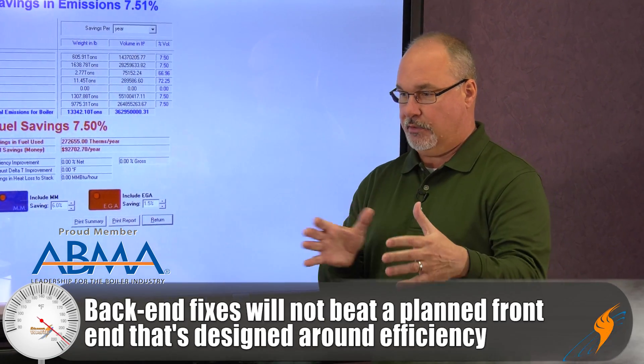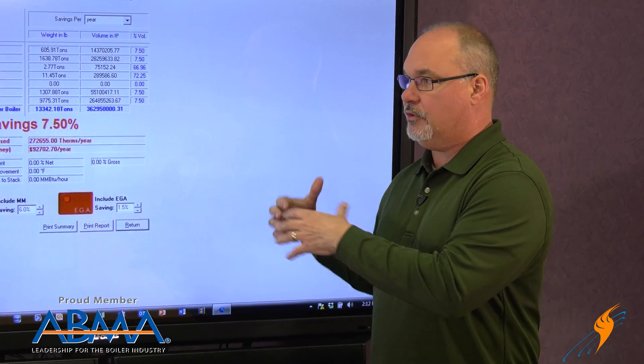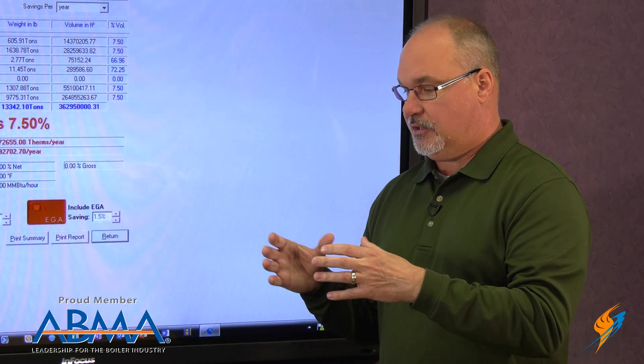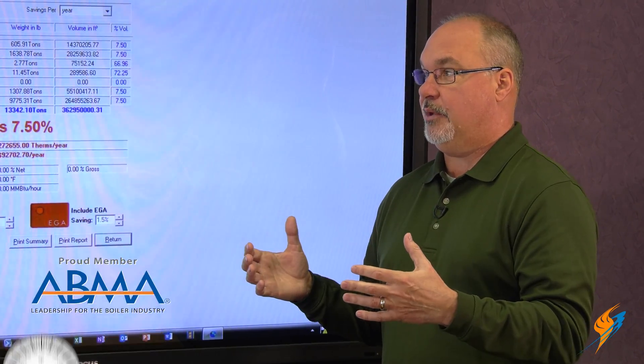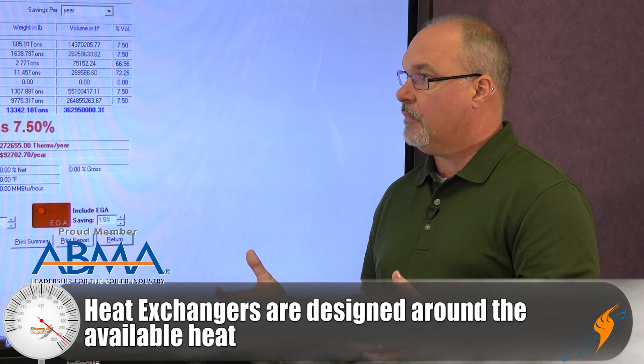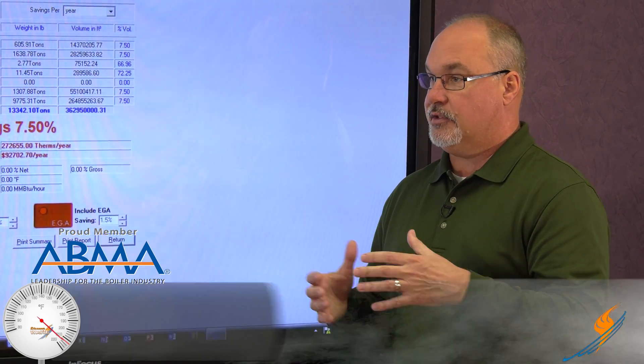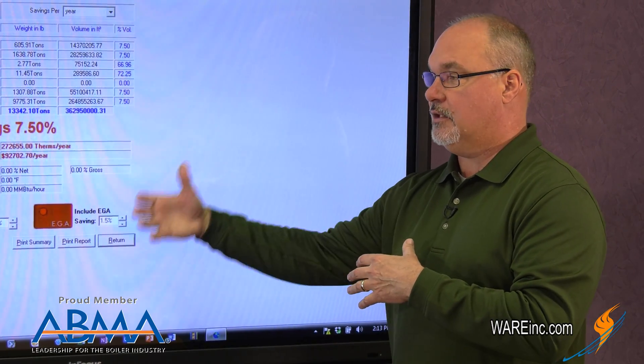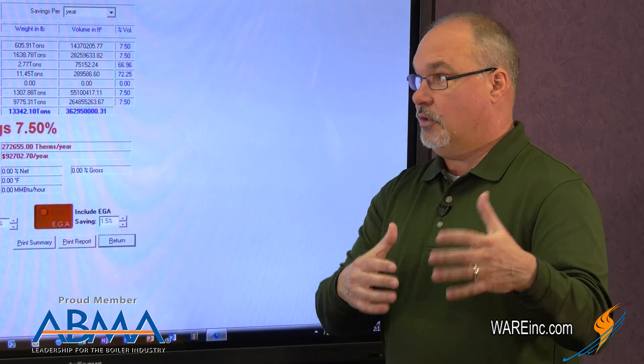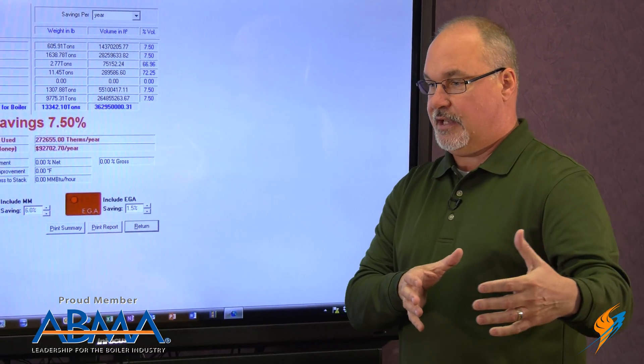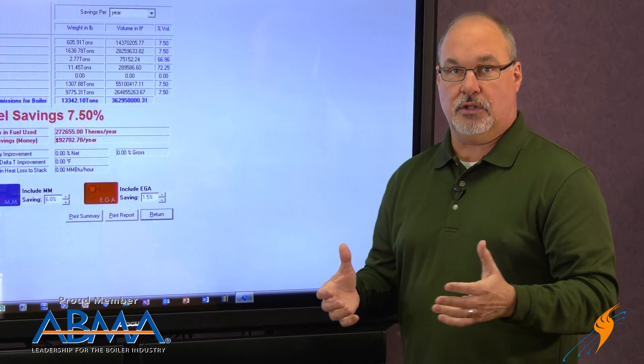When you have a boiler — which is a heat exchanger — an economizer, or whatever else you're doing downstream, none of those things will actually get you what you missed out on the front end. The reason is that heat exchangers are designed around one major parameter: available heat. So as a best practice we try to get the front end right so that the heat exchangers and other heat recovery systems can do the job they were intended to do. There's a variety of things in that process that can have an impact on all of those other tools.